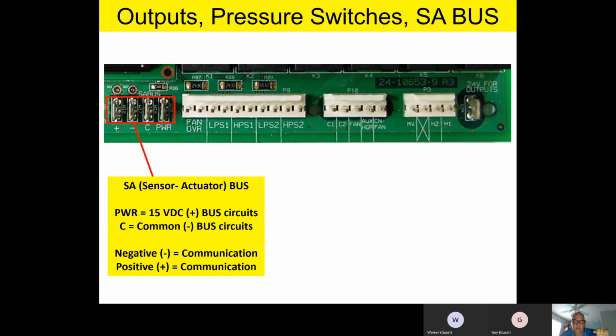Now, when it says negative, what it's really talking about is pulling that down to 0. So common is a reference to chassis ground. Power is 15-volt DC, reference to chassis ground. Plus and minus on the communication would be to communicate with things that are on the SA bus. Again, things that could be on the SA bus would be, for instance, an economizer hooked up to the SA bus. And later on, when we look at that little 6-pin plug where we plug in our MAP device, it's actually communicating on the SA bus as well. Any questions on the SA bus before we continue? Is everybody good?